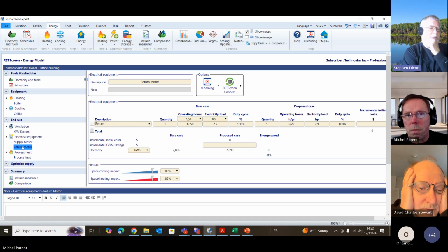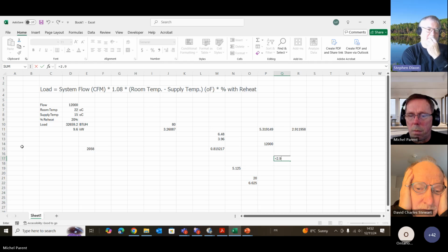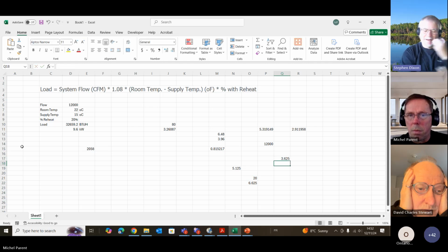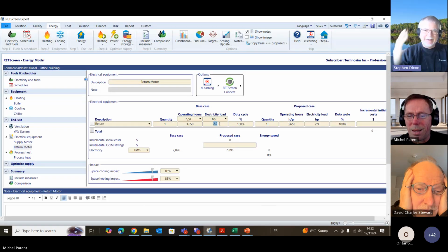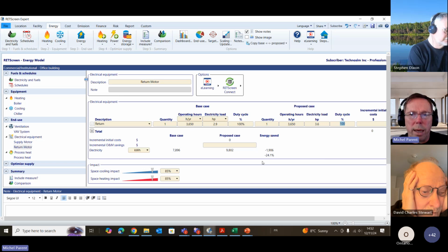I remember the first time I ever met you, after the original time I met you, Michel, and we were doing this calculation in a hospital, and you were shaking your head over why they have these heat wheels on these constant or these variable volume systems, and you go, they're not going to save any money. No. Only when you have lots of outside air. You have to be at 30% plus outside air to get any kind of savings.